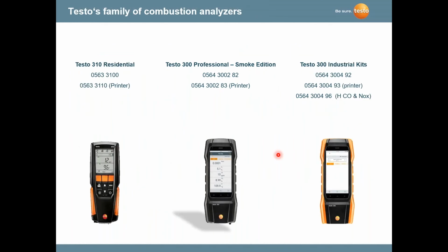combustion analyzers. One thing about combustion analyzers is it depends on what market or application you're in. A residential combustion analyzer is mainly for residential furnaces, oil and gas furnaces. In our professional series, you get into a commercial grade. Then we have what we call an industrial grade, which has a high carbon monoxide sensor in it and also a NOx sensor. So you've got good, better, best, and it's based on pricing, and ITM can do a better job with pricing than me on the Canadian side. This happens to be what I consider a residential analyzer, which is going to be the least expensive. Then there's the middle range analyzer, and the top line is basically what I'm talking about here.